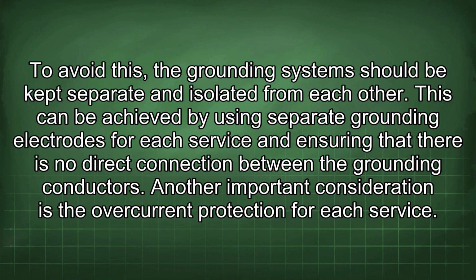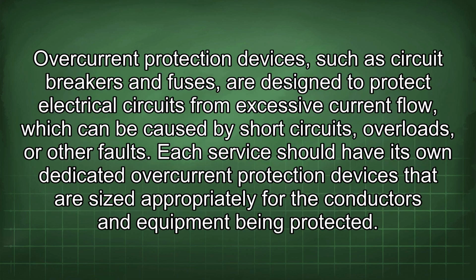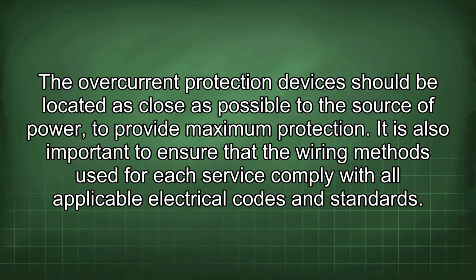This can be achieved by using separate grounding electrodes for each service and ensuring that there is no direct connection between the grounding conductors. Another important consideration is the overcurrent protection for each service. Overcurrent protection devices, such as circuit breakers and fuses, are designed to protect electrical circuits from excessive current flow, which can be caused by short circuits, overloads, or other faults. Each service should have its own dedicated overcurrent protection devices that are sized appropriately for the conductors and equipment being protected. The overcurrent protection devices should be located as close as possible to the source of power to provide maximum protection.